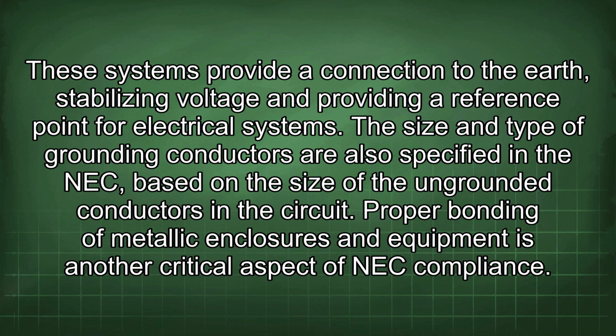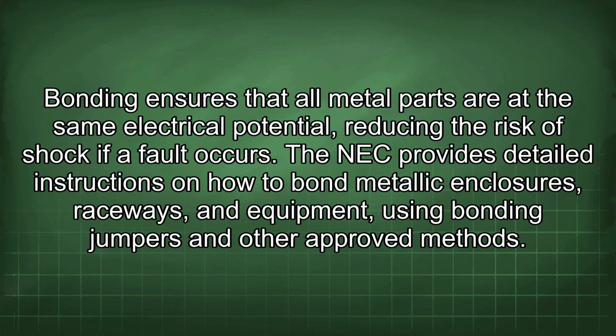The size and type of grounding conductors are also specified in the NEC, based on the size of the ungrounded conductors in the circuit. Proper bonding of metallic enclosures and equipment is another critical aspect of NEC compliance. Bonding ensures that all metal parts are at the same electrical potential, reducing the risk of shock if a fault occurs. The NEC provides detailed instructions on how to bond metallic enclosures, raceways, and equipment using bonding jumpers and other approved methods.